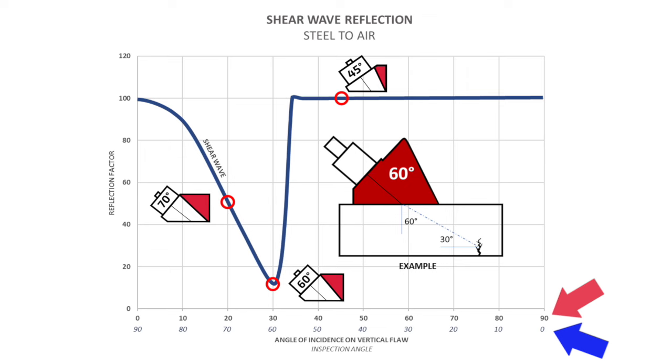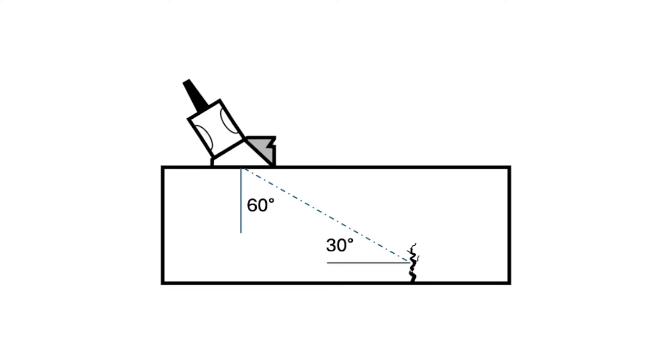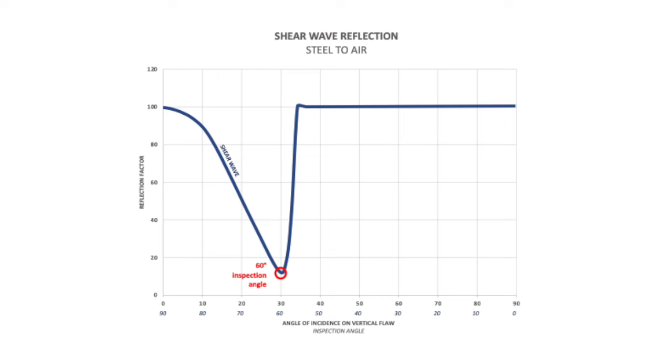Above that is the incident angle on a vertical flaw. If you are shooting at 60 degrees and you have a vertical flaw, like a notch in a block, what's happening is even though your beam is at 60 degrees, you're actually hitting that flaw at 30 degrees. And we get a really weak shear wave return at that angle — because most of the shear wave is converting into long waves.